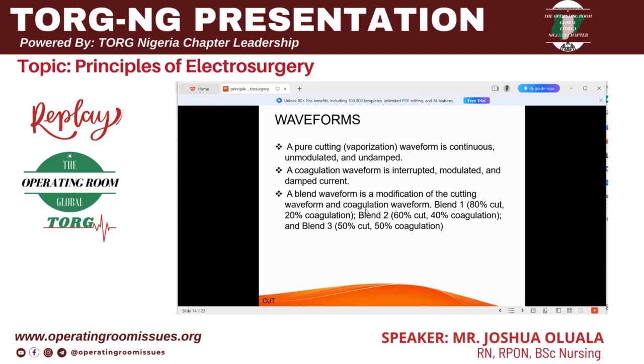But in the case of coagulation, when you are coagulating, what kind of waveform is applicable to coagulation? An interrupted one. So in this case, it's not continuous, it's interrupted. Interrupted, modulated, and dampened currents. That's what we see in coagulation. But when it comes to blend waveform, what do we see? It is a modification of both cutting and coagulation, which is most of the time what we actually use, because in the case of monopolar, you just want to have a balanced waveform, and you can see the percentage. So when your diathermy is in blend one, you have 80% cut and 20% coagulation.